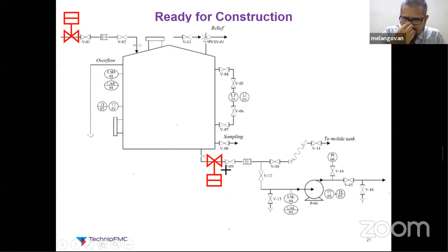Remember the Jaipur incident, the IOCL Jaipur incident, the tank pump incident. There they had the valves, even though it was a motorized valve, but that needed to be activated on site. It could not be activated remotely from the control room. A person needed to go to the site and push the button. Unfortunately, before that site activation happened, the diesel released from the tank formed a flammable gas cloud, so that no person could enter. So what happened ultimately? The entire tank content leaked out, which resulted in a massive fire incident. A costly lesson learned for India.